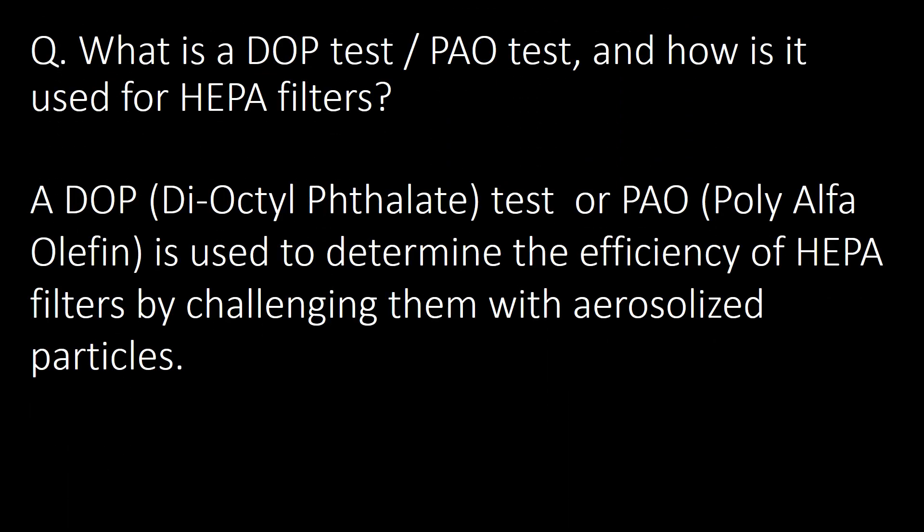What is the DOP test or PAO test and how is it used for HEPA filters? The DOP (dioctyl phthalate) test or PAO (poly-alpha olefin) test is used to determine the efficiency of HEPA filters by challenging them with aerosolized particles.